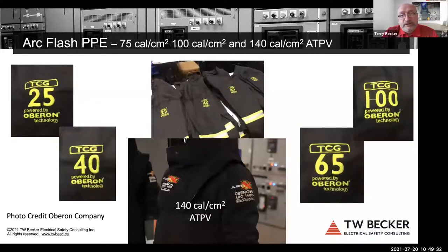And as I mentioned, the ATPV of arc flash suits, there's probably 6 or 7 or 8 vendors now that have 75 to 80, but only Oberon company still has 100 and 140 cal. And again, you can assess using this PPE, using risk assessment, and it's valid. It's valid. And we need a balance between engineering incident energy reduction methods and PPE.